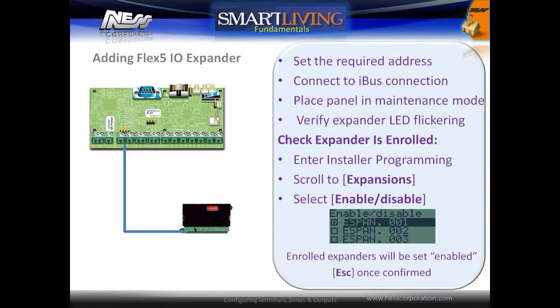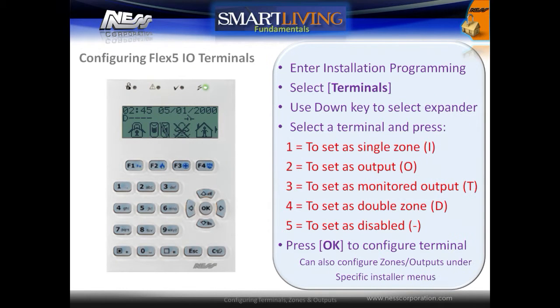To verify that the expander is enrolled, enter into installation programming, scroll to Expansions, and select Enable/Disabled. Enrolled expanders will have a check next to them indicating they're enabled. Press Escape once confirmed. Configuring terminals on expanders is the same process as configuring them on the main board: enter installation programming and select Terminals.